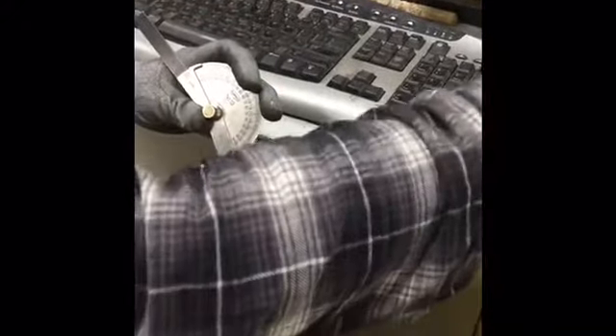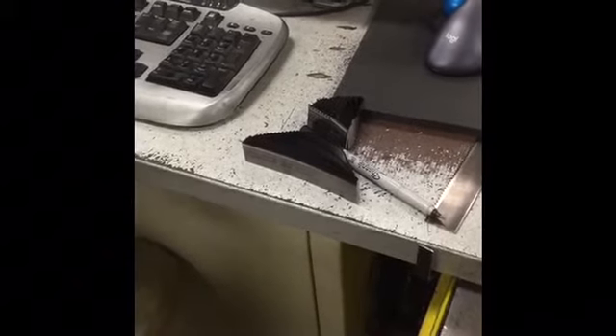Once you get to 15 degrees, it's just going to start spitting out these small angles. Make sure you keep everything in order, because if they get mixed up, you're going to put the wrong number in the wrong area, and it's not going to calibrate properly.